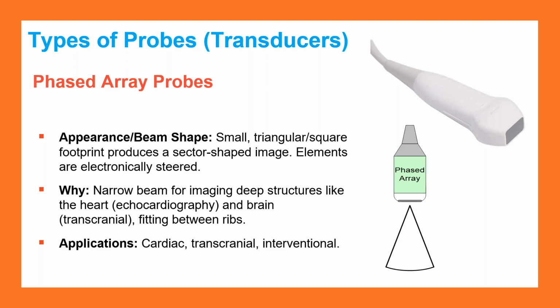Phased array probe. This is a unique probe. The phased array probe is normally a cardiac probe, and it's important that we realize that they're primarily used for cardiac. They can be used for the abdomen as well, but most of the time it's a cardiac probe, okay, primarily. But this is your image shape. It looks like a piece of pie. They call these probes sector probes or vector probes as well. So you may hear your sonographers say my sector probe's not working, and it's because they've learned it by a different naming convention, but they're the same probe: sector, vector, and phased array.